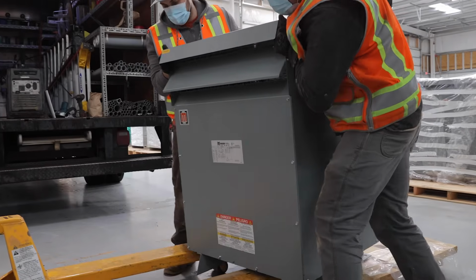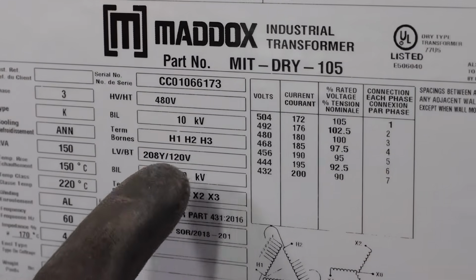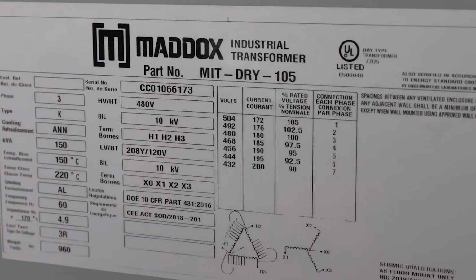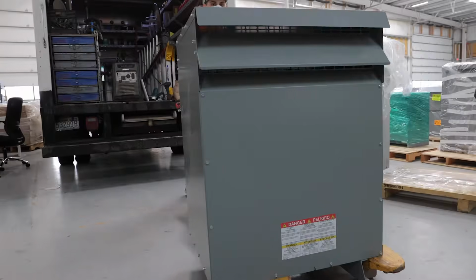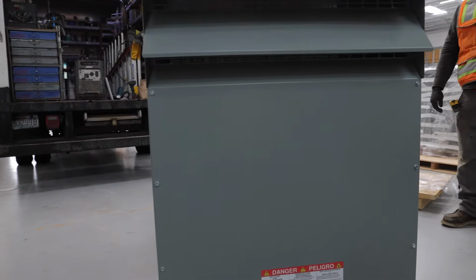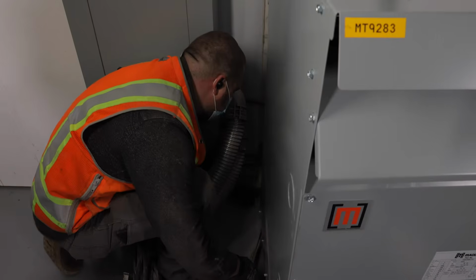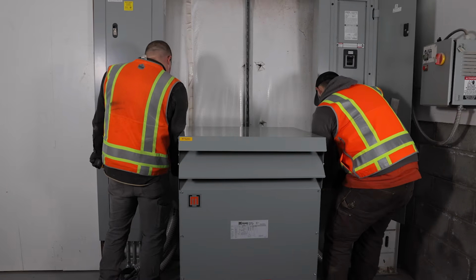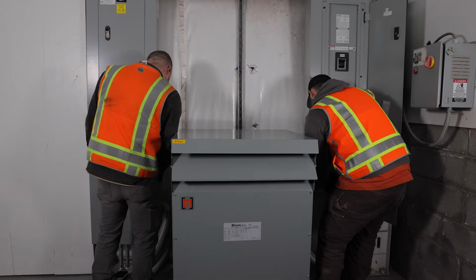The new transformer is then removed from its packaging and shipping pallet. All nameplate data is reviewed to ensure compatibility, paying special attention to ventilation clearances. The transformer is then moved into place. The electricians check the distance from the wall on both sides to ensure that minimum clearances are met.